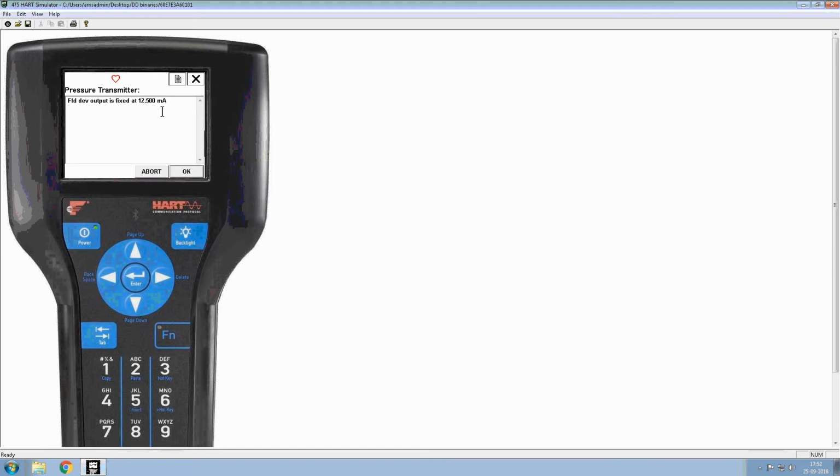If the values match, the transmitter and the loop are configured and functioning properly. If the values do not match, the current meter may be attached to the wrong loop, there may be a fault in the wiring, the transmitter may require re-ranging, or the reference meter may be malfunctioning. Click OK on the method screen to go back to the output selection screen.